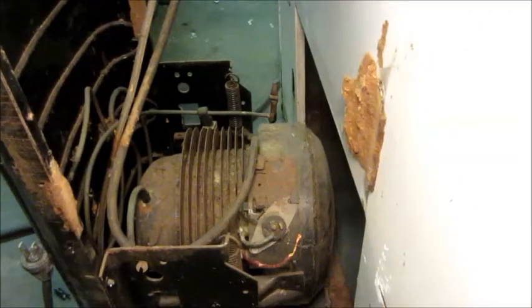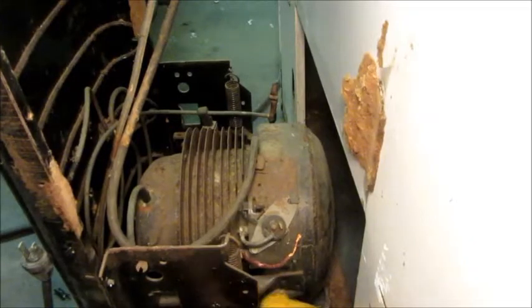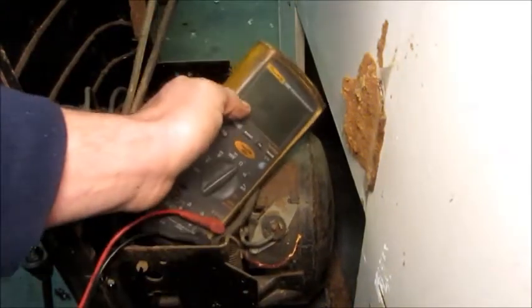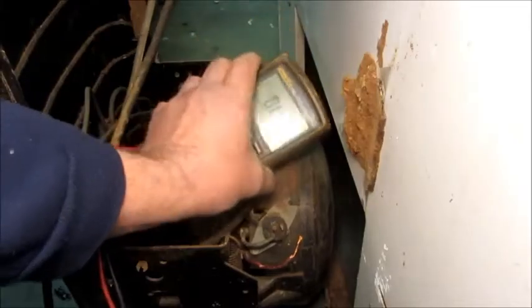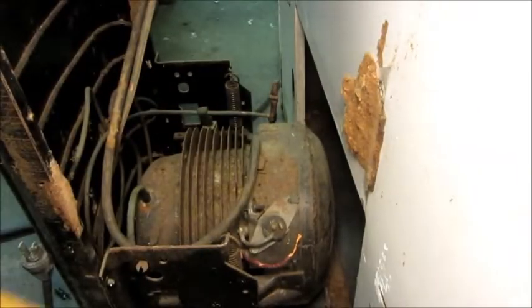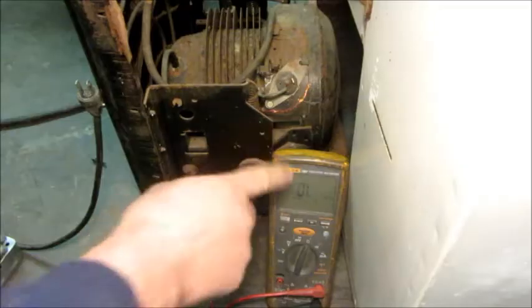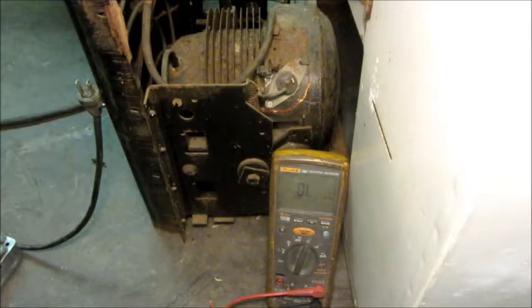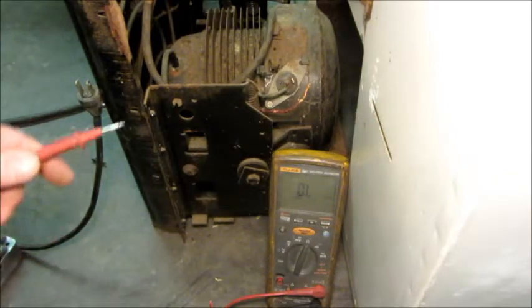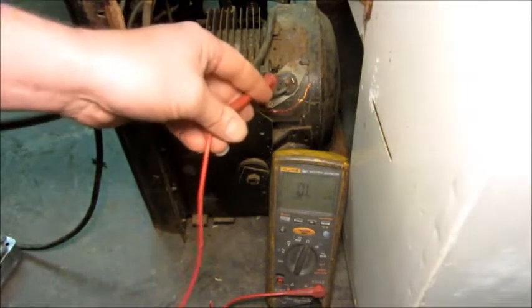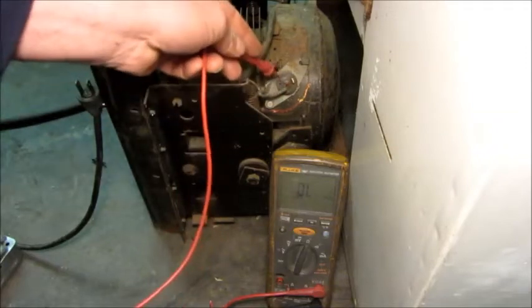So the first thing I'm going to do to determine viability of the compressor, I'm going to check the resistance of the motor winding. The way this Westinghouse is built is awkward, but I want to try to get the meter on camera. Now that I got the meter on screen, we're going to check the resistance of the compressor motor.